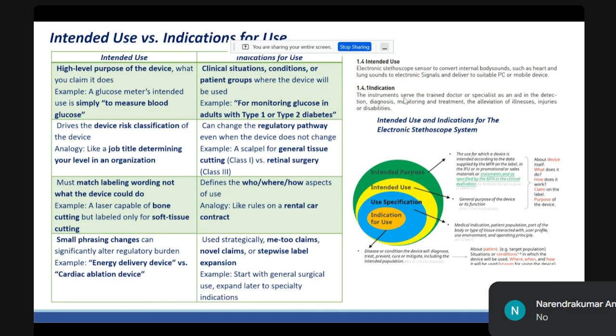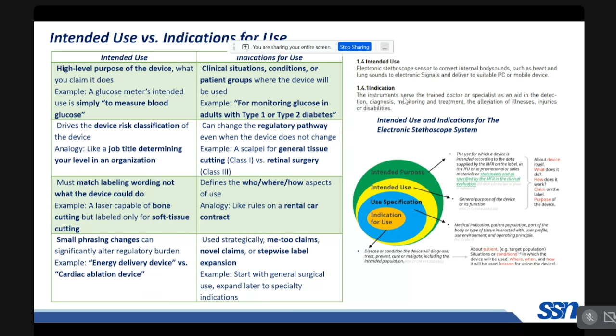it just says that it measures the oxygen saturation, but it doesn't mention any clinical condition or the use environment. Okay, so if it says that this smartwatch measures oxygen saturation in a clinical environment and for the detection of specific pathologies, in those conditions, that becomes a medical device. Okay, so just to summarize, this intended use and indications of use basically determine the class of the device and the regulatory pathway of the device. Okay, so moving on to the next slide.